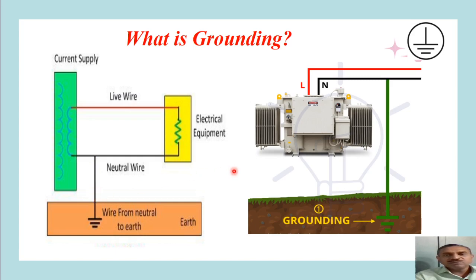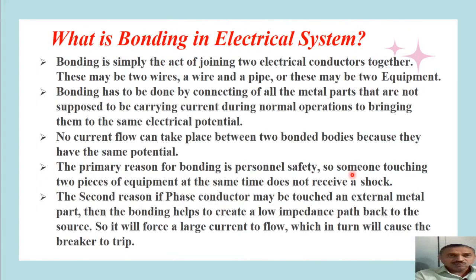The same is elaborated on the right side through the physical diagram. The neutral of this distribution transformer is grounded. So point to be noted is that in grounding we are making the neutral to be connected to the earth so as to act as a return path of current in the event of the fault. Now one more term is used in electrical system, that is the bonding.